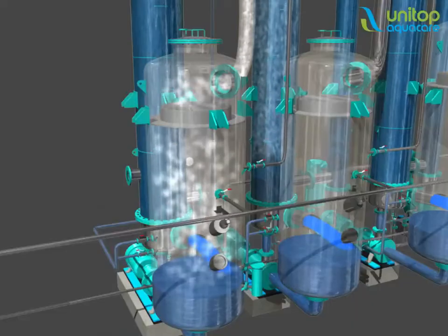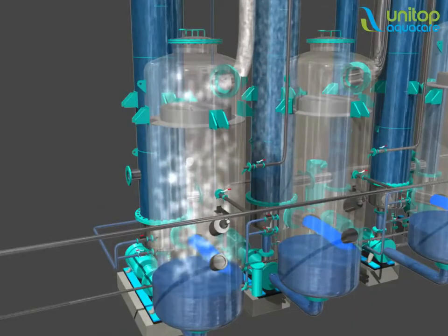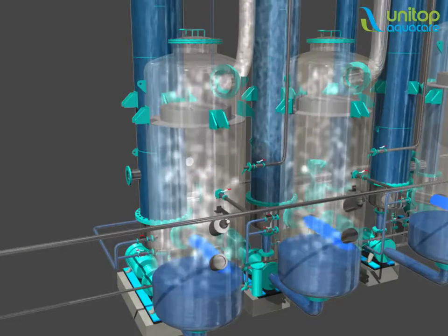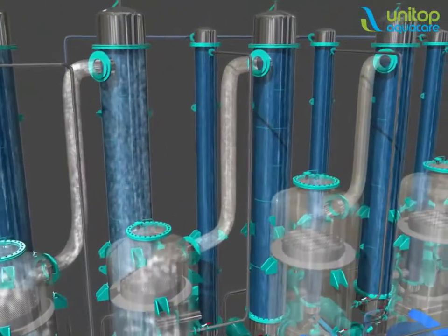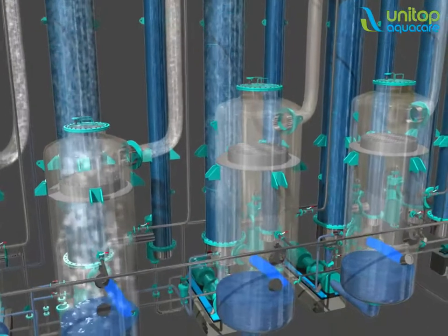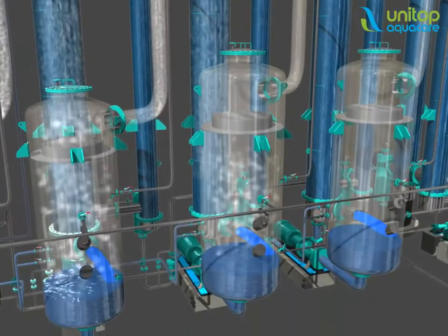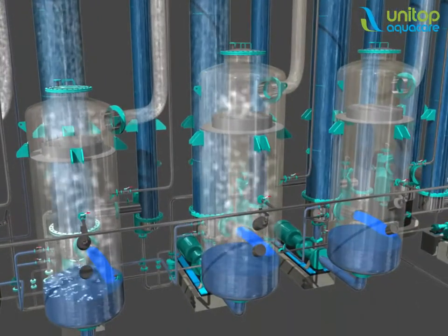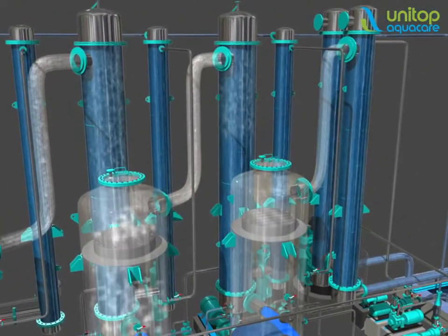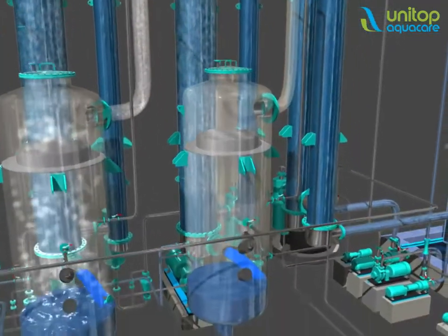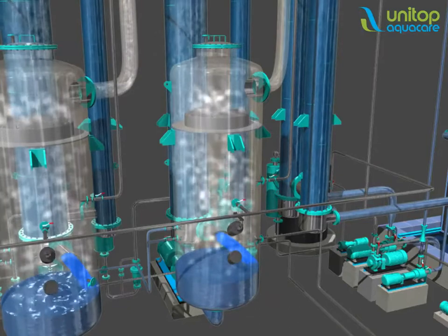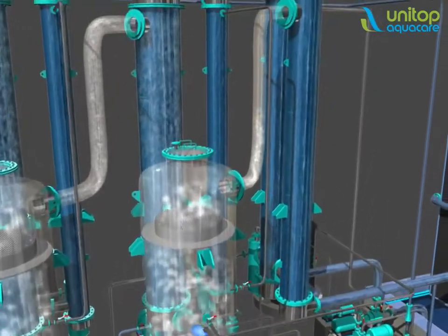In the first flash vessel, some water from the RO reject gets flashed and is converted into vapors. These vapors are carried into the next heater's shell side as a heating media by vacuum, and again the RO reject passes through the tubes, and thus there is a heat transfer between shell side vapors and tube side liquid. Subsequently, vapors are separated in a flash vessel, and the whole process is repeated in successive stages.